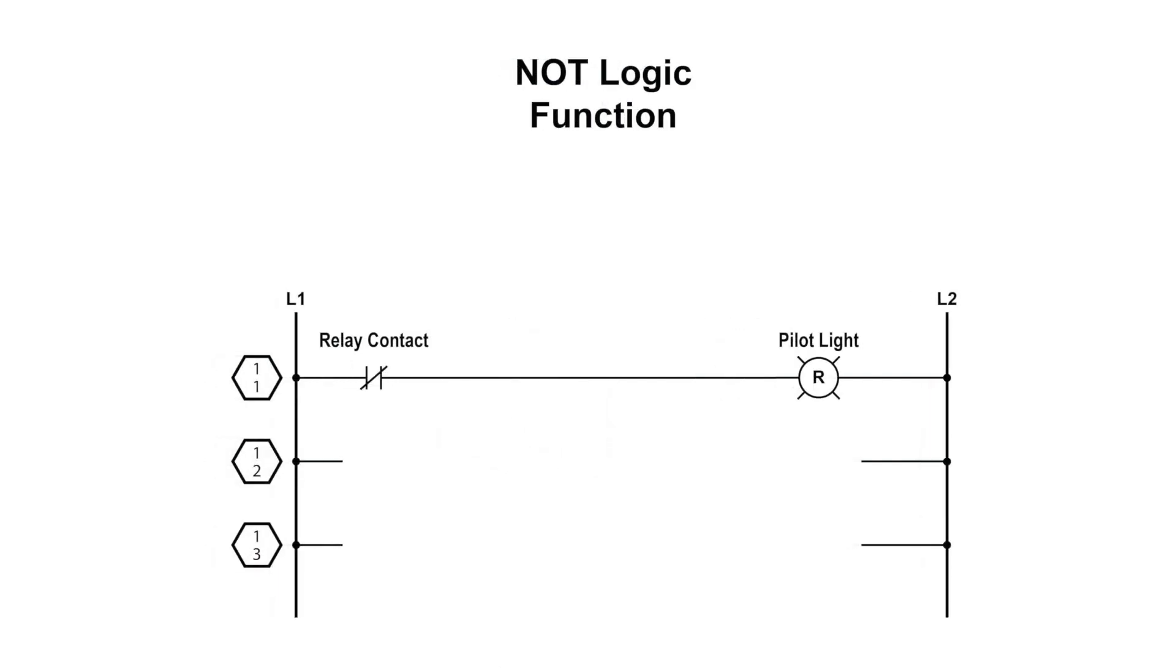The NOT function uses a single normally closed input device instead of a normally open input. The NOT logic energizes the load when the control signal is off. The example shows a relay coil with an indicating light. Its purpose in this instance is to indicate that an area cannot be entered due to a motor running.